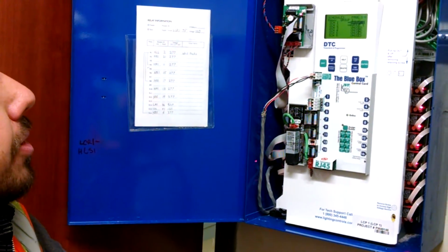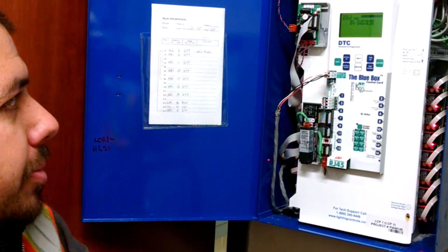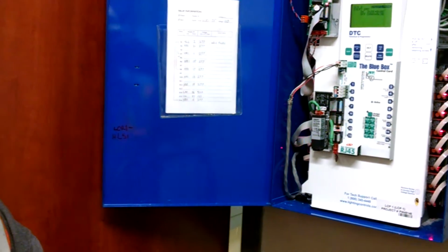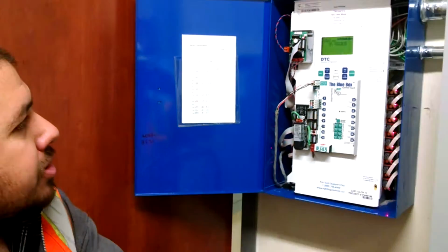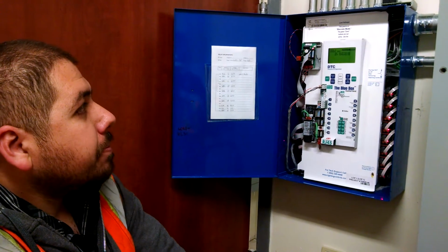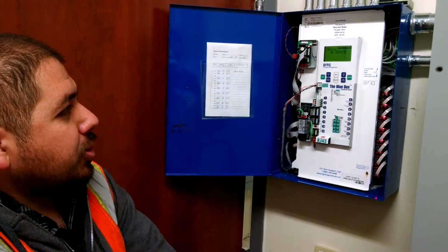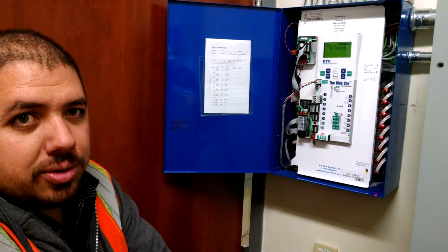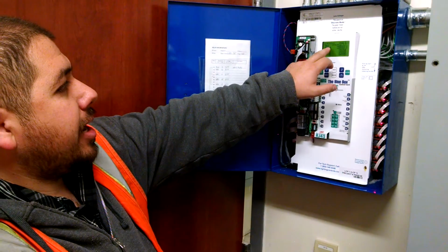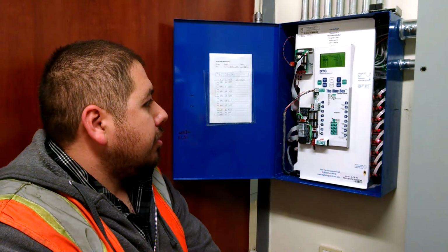Just press yes. Okay? I like to build in a backup to the photocell, and that's a time clock. This thing has built-in astronomical clock features. So the backup is lights will turn on at dusk, and they'll turn back off at dawn plus a half hour. The intention of that is that if the photocell fails, the astronomical clock can take over operation and get the lights working until the photocell can be replaced. And that astro clock backup is controlling the same group number 1 as the photocell is.